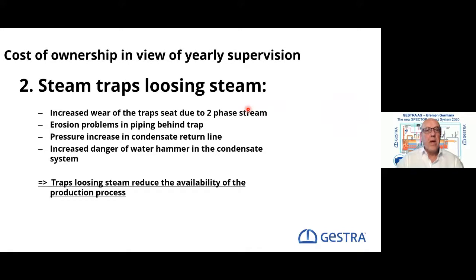If the steam trap loses steam, then we have increased wear of the trap's seat due to the two-phase stream. Under a pressure drop of 40 bar, it takes only 1-2 weeks, and the steam trap is more or less fully open, and we have a real problem in the condensate line.